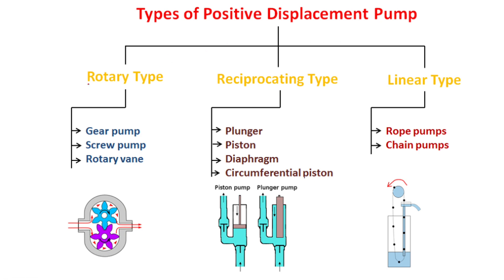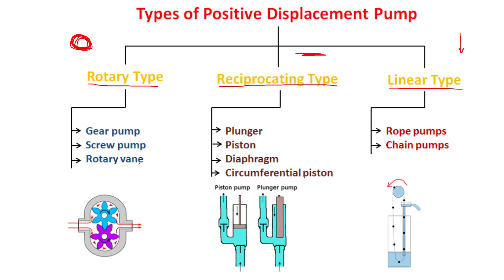The first group is the rotary type, group number two is the reciprocating type, and group number three is the linear type. Rotary type means we have rotary motion or rotation. Reciprocating type means we have reciprocating motion. Linear type means it moves linearly in one direction — it's not oscillating left and right like the reciprocating type. For the rotary type we already talked about gear pumps; we also have screw pumps and rotary vane pumps. For reciprocating types we have the plunger pump, piston pump, diaphragm pump, and circumferential piston pump.